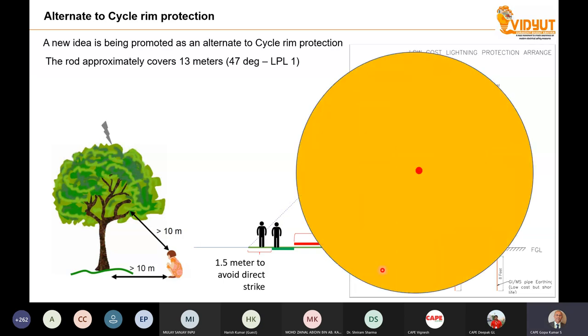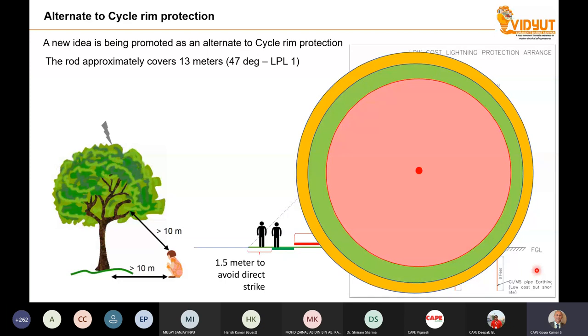So if we look from the actual view, this is the rod. The orange color is the claimed protected area. First 10 meters, you cannot go because of the step potential. Then you have about 1.5 meter, which is actually protected. The last orange place you cannot use because you will get a direct hit. So if these systems are installed, during lightning people should run towards this particular rod. Then they have to find out where this 1.5 meter is and stand on it. If you go closer, there is a problem. So such dangerous systems are proposed across India.